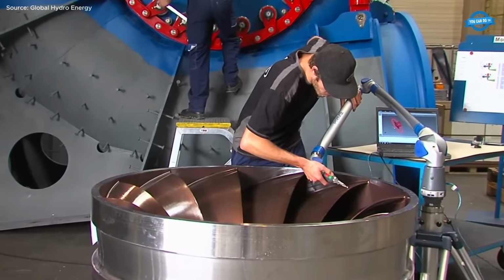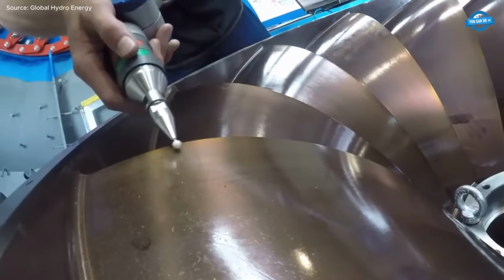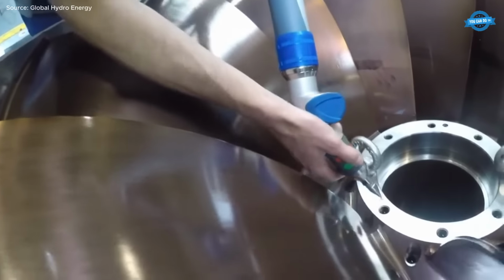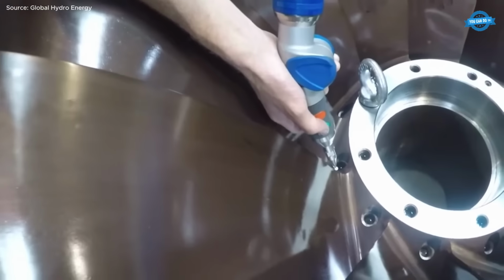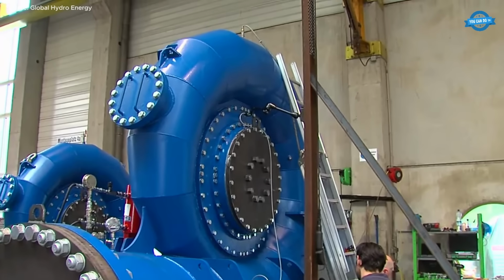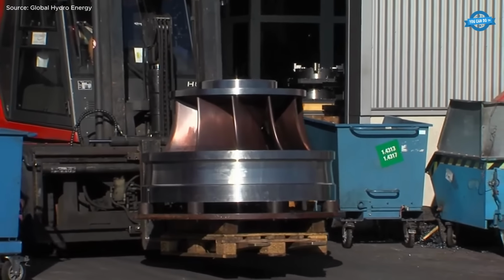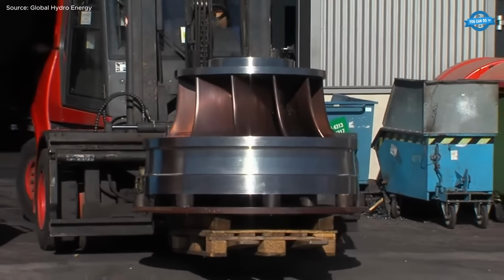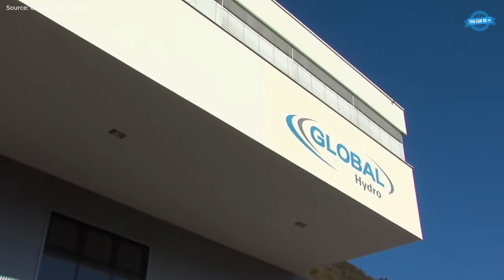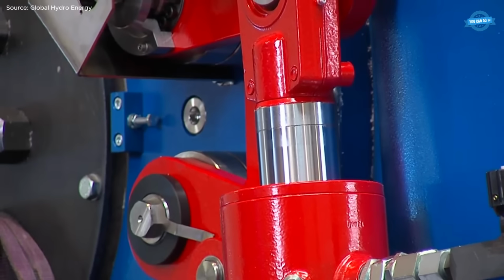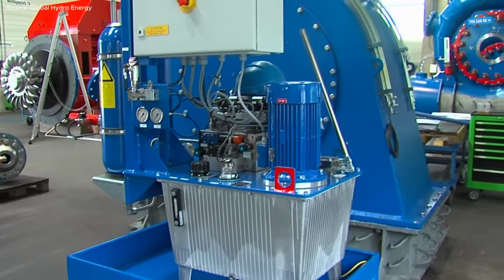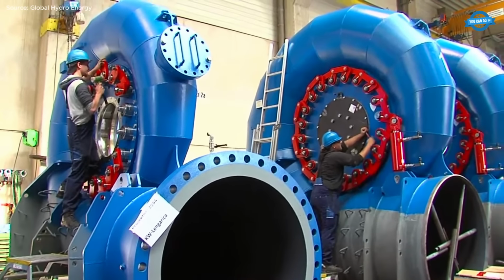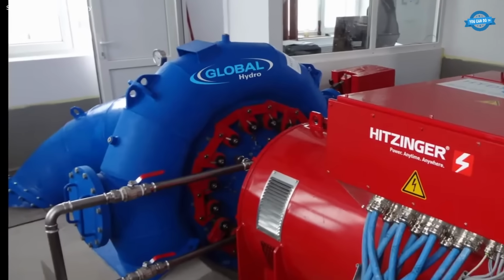After machining, surfaces are hand-polished, and split runners undergo heat treatment. Each runner is dynamically balanced to ISO standards. Digital 3D measurement verifies contour accuracy before assembly. Final pressure testing of the spiral casing ensures weld integrity and structural safety. The result is a precision-engineered Francis turbine designed for long-term, high-efficiency hydropower generation.